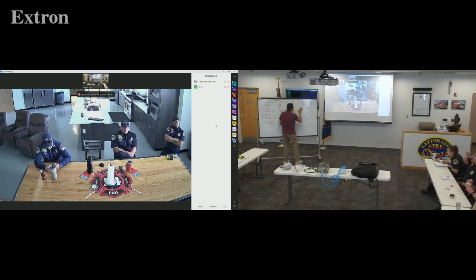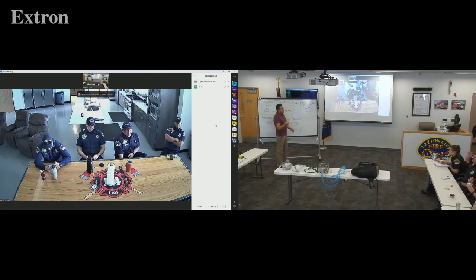Yeah. All right. Now, I was telling everybody that because respiratory rate is directly related to the I to E ratio, if you move that rate to 10 to 12, you're cutting this number, right? Because you're utilizing more time out of the 60 seconds in order to fit these 2 extra breaths. Now, the question was, I'm not understanding why if I have a respiratory rate of 10 or 12 and this number automatically moves, how can I just manipulate this number as well? You can, because when you manipulate this number, let me start over. When you manipulate the respiratory rate and the I to E ratio moves automatically, the ventilator just calculates in an even way how to separate the inspiratory time from the expiratory time, regardless of how much time it gives it. It gives it 0.8 of a second to 3.5 seconds or whatever.